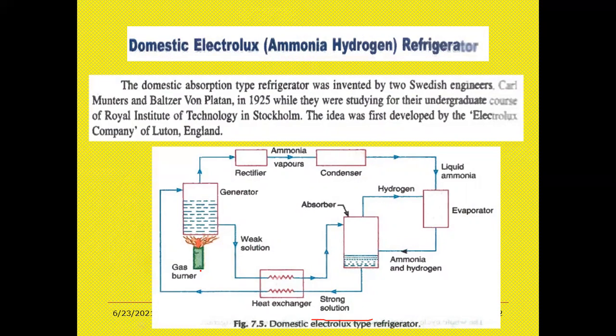the gas burner is heating the solution, thereby this solution goes into the rectifier and it rectifies the ammonia vapors. Ammonia vapors come out and go to the condenser. From the condenser it goes into the evaporator, right? The liquid ammonia goes into the evaporator and then into the absorber. So here we have an absorber, whereas in the vapor compression system we have a compressor, right?